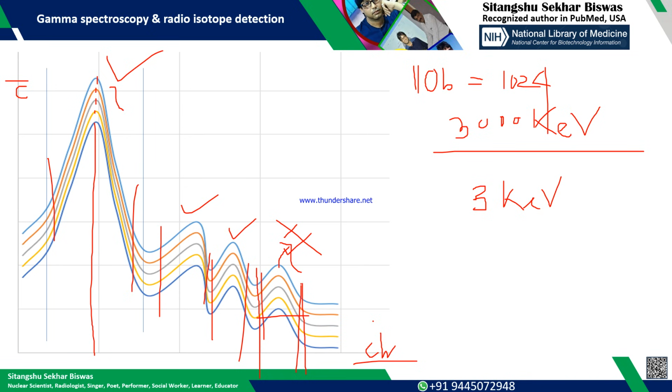This causes a current flow through the external circuit that is detected as a pulse. The height of the pulse shows the energy: more energy, more excitation, and more excitation means more electrons through the external circuit. So pulse height represents the incident photon energy coming from a particular radioactive nucleus.